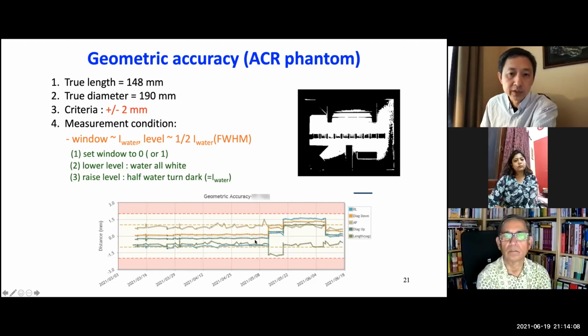So actually it made the geometric accuracy worse. However, it's still within the ACR limit. It's within the red dashed lines here, which are plus or minus 2 millimeters. So they are still within the ACR limit, but in our institution we require 1 millimeter, or we try to make 1 millimeter, which is better than the ACR limit. So we asked the engineers to come in to recalibrate, but that made another direction worse. This direction is better, but the other direction was worse. And then they came in again and made everything good.